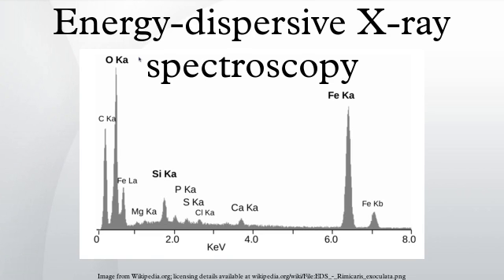EDS is often contrasted with its spectroscopic counterpart, WDS. WDS differs from EDS in that it uses the X-ray's diffraction on special crystals as its raw data. WDS has a much finer spectral resolution than EDS and also avoids the problems associated with artifacts in EDS. In WDS, only one element can be analyzed at a time, while EDS gathers a spectrum of all elements, within limits, of a sample.